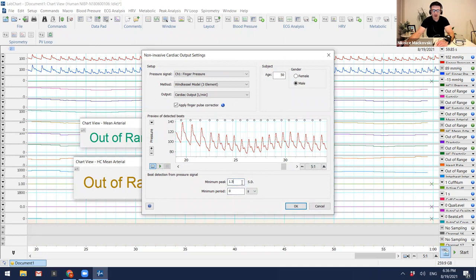The minimum peak is 1.5 SD, and we don't have a minimum period here. So this is detecting it fairly easily. For finger pressure, it's using channel 1, and the method is a Wesseling model here. So you can choose between these two. Wesseling requires age, so my age is 35, and you can apply this here. So you can choose between cardiac output, stroke volume, estimated flow, or total peripheral resistance.